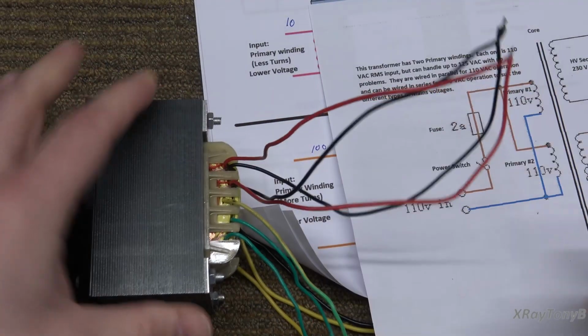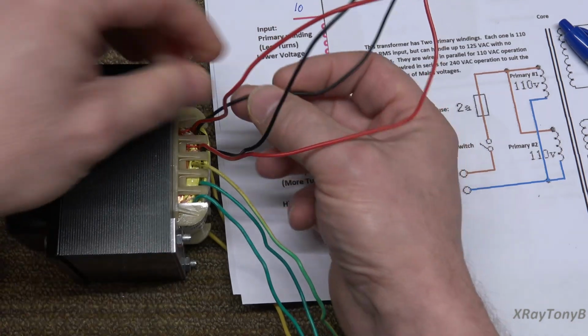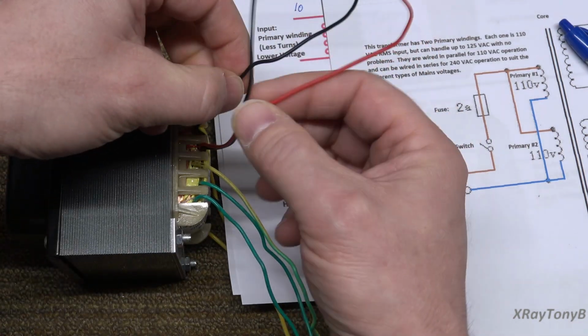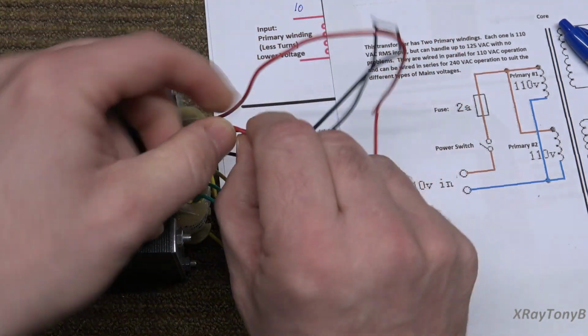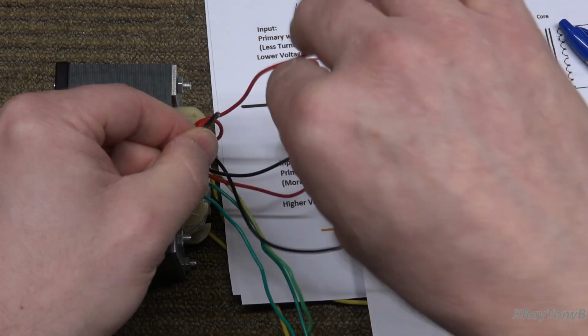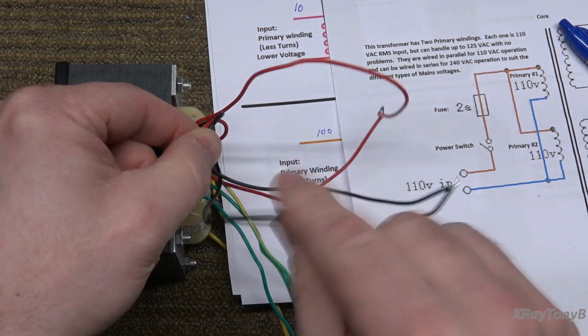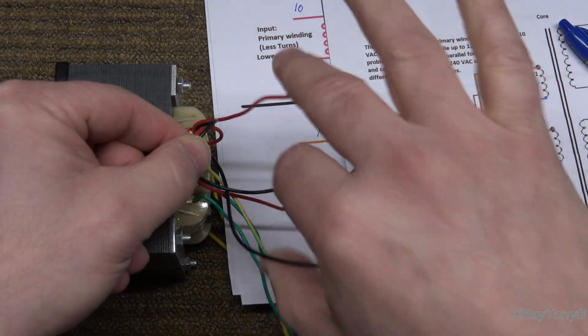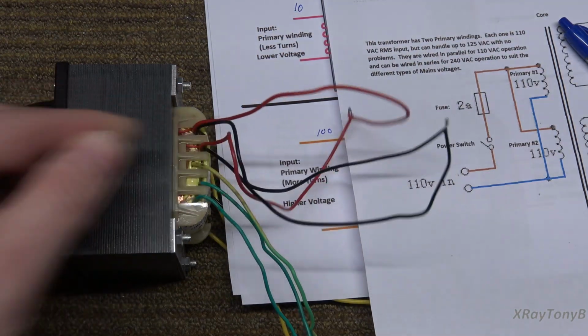So what we'd do is take this black wire from this winding and connect it to this red wire from this winding, tying them together. Then these two wires right here would be your 230 or 240 volt input, wired in series.